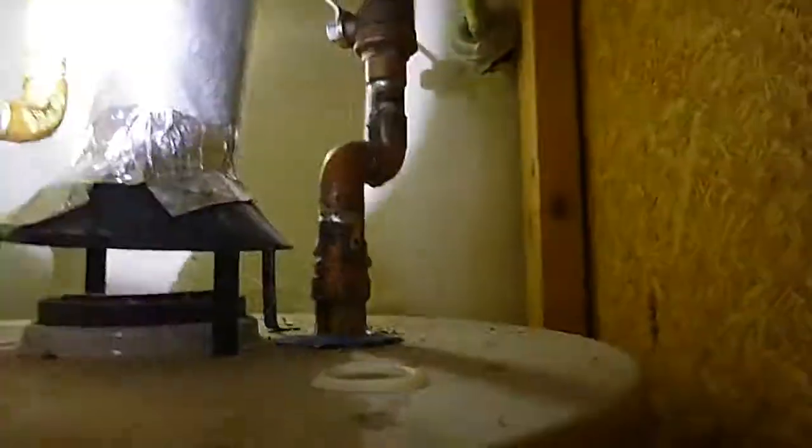Water heater is that gas, the flexible gray gas line I was explaining. It does have a safety pan, does have a vacuum breaker inside. That's kind of nice. You should not have tape on your flue. Okay, the flue should fit without tape. Dielectric unions, insulation should be next to the tank on the water supply lines and on the TP valve. The upstairs one is 40 gallons. It was manufactured in 2008. And there's a care and use manual right there.